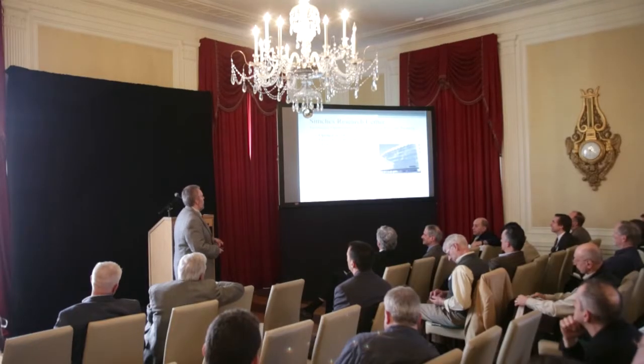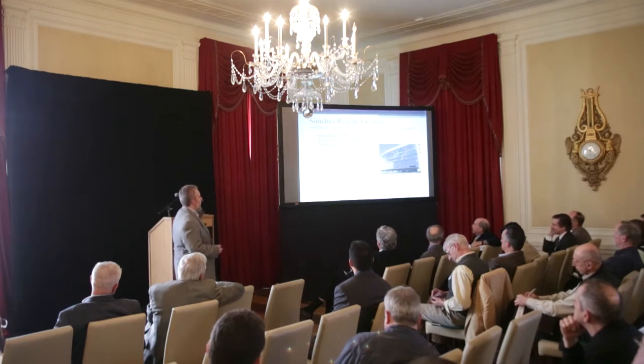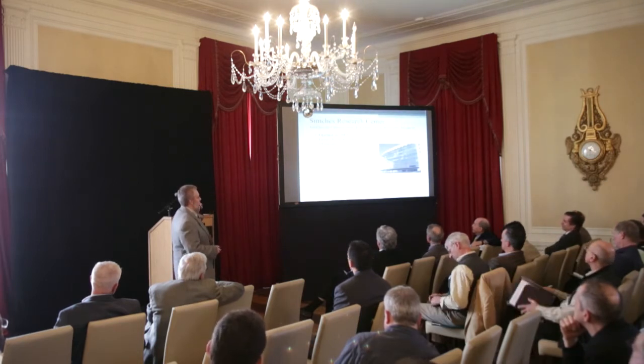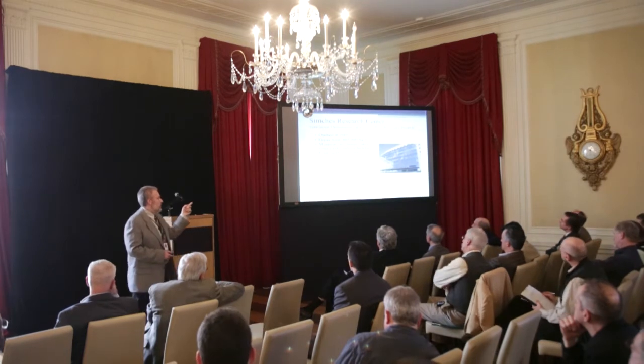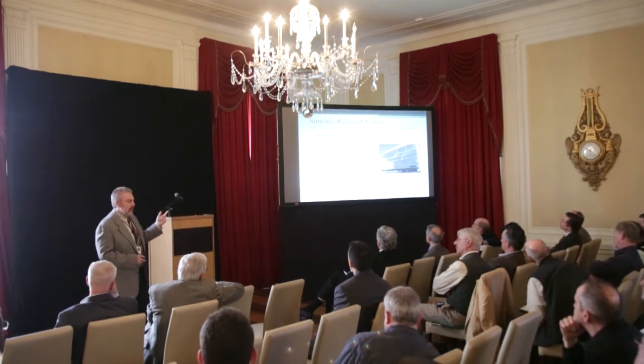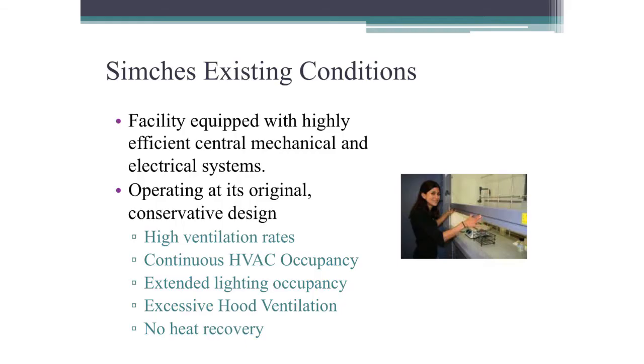So we looked at the minimum air changes. We implemented occupied, unoccupied. We looked at a heat recovery system to preheat the air, and I'll show you a slide on that. So the facility, like I said, was equipped with highly efficient, best available technology. It had high ventilation rates. It had continuous HVAC occupancy, extended lighting occupancy, excessive hood ventilation, and no heat recovery. So those items right there are the 5 items that we tackled.